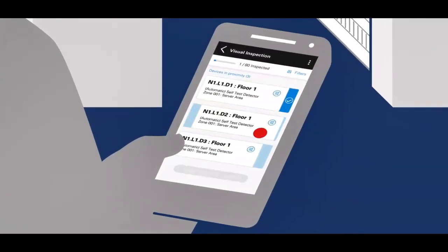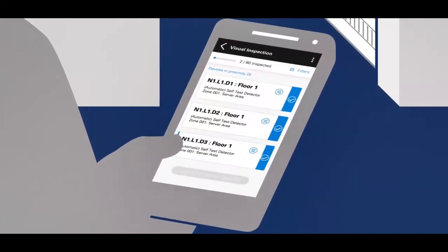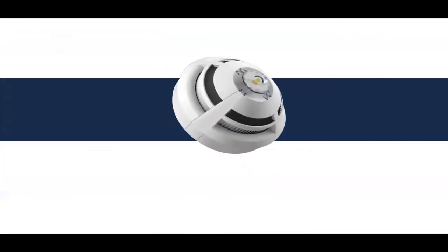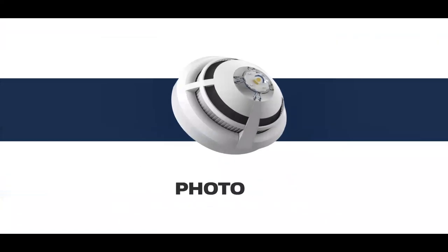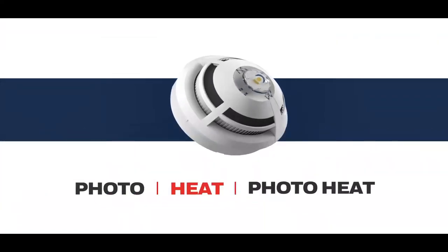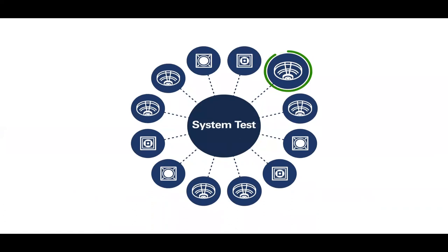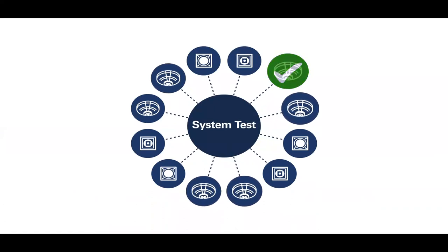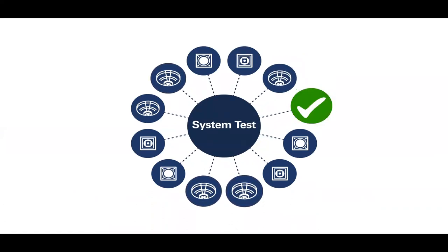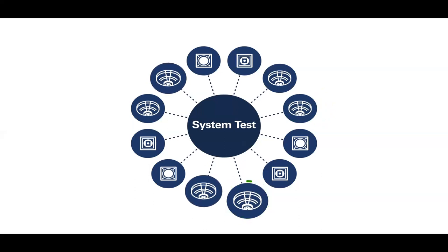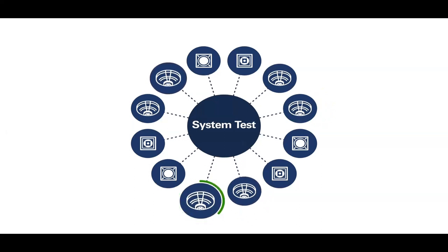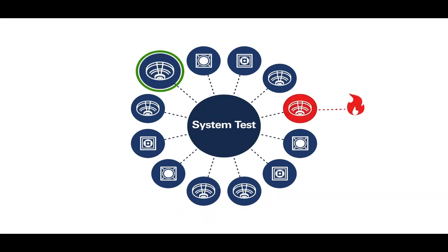This is showing how, when he walks up to the device to check it, he can see it. He's visually looking at that device. He knows it's self-tested because it's sending a note to him on his panel. He's walking up now. He can see it. When he sees it, he swipes right and it shows that it's been tested. These are the various devices on the loop, and as he's walking around and testing them, it will do it in the order that he's doing them.